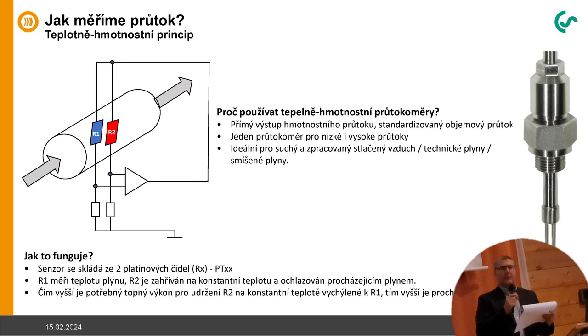You can measure both. You can measure the small leakage rate during the weekend, but you can also measure the high flow rate during manufacturing during the week. So it's ideal for compressed air, technical gases, mixed gases, and so on. How does it work? So the working principle is as follows.